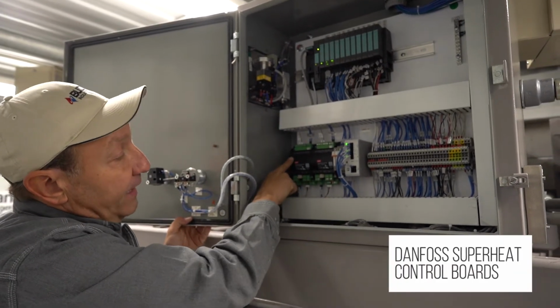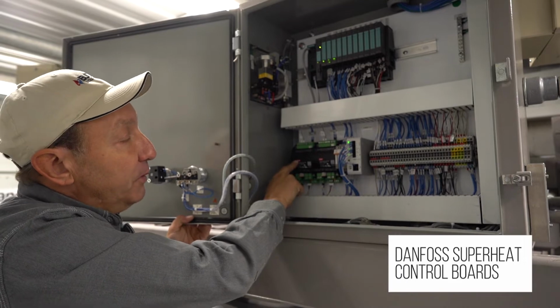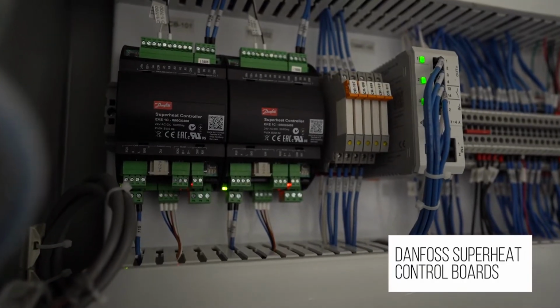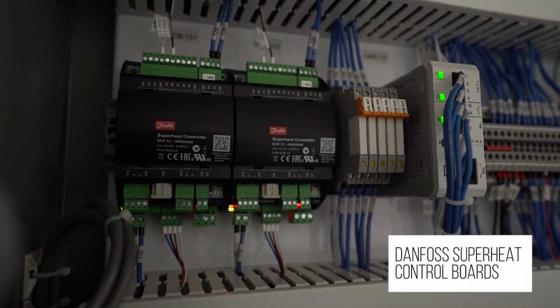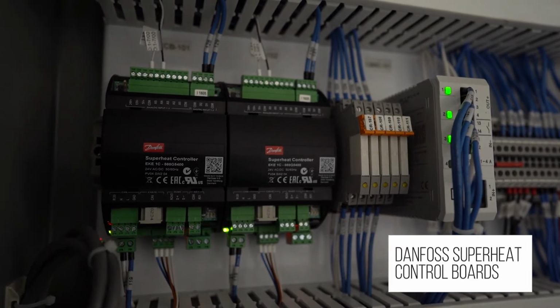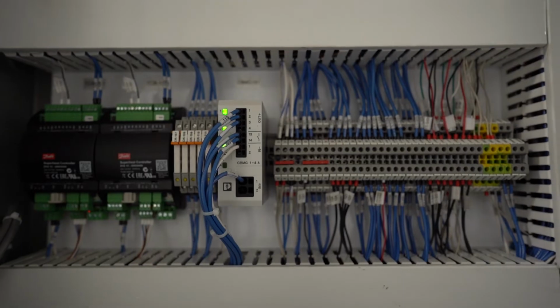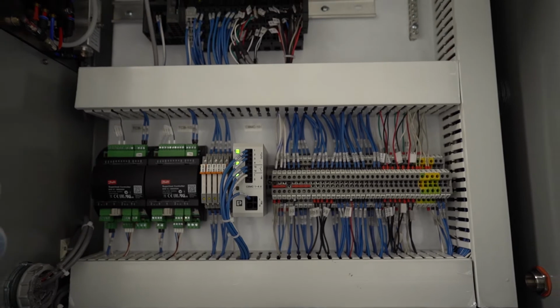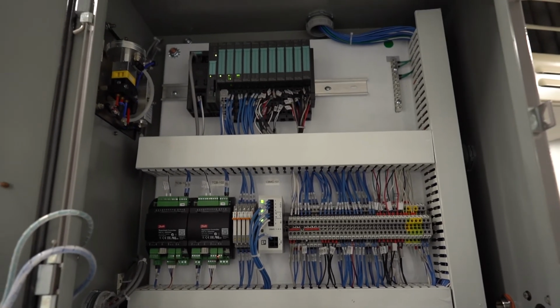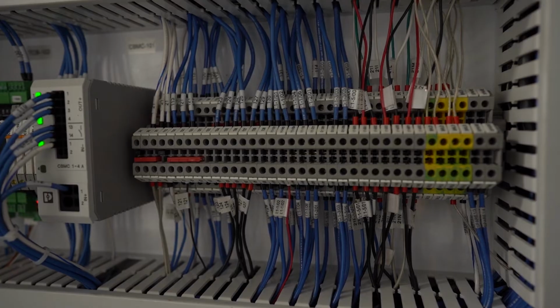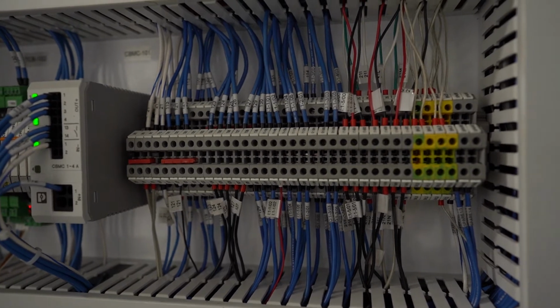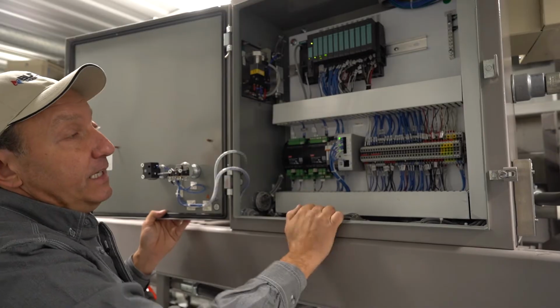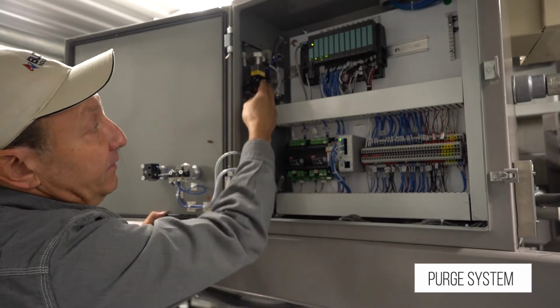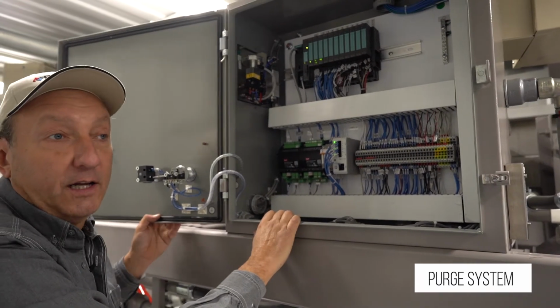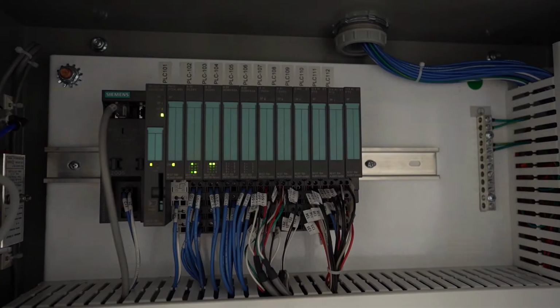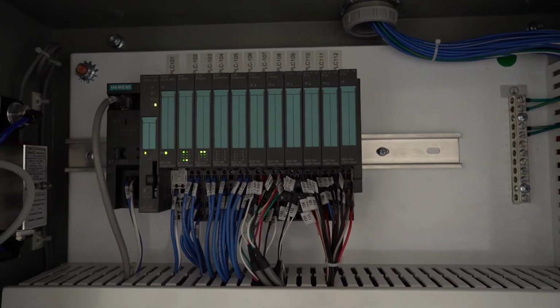These are Danfoss superheat control boards. These controllers control our electronic expansion valves for our refrigerant flow through the evaporator. We have a series of relays, and everything in this cabinet is 24 volt DC. It's all safe and easy to maintain and troubleshoot. Everything's labeled, everything's identified. Each one of these enclosures also has a purge system at 1-inch water column to keep all the electronic components separate from the propane.